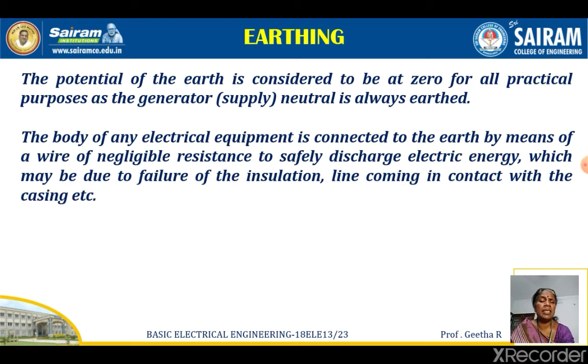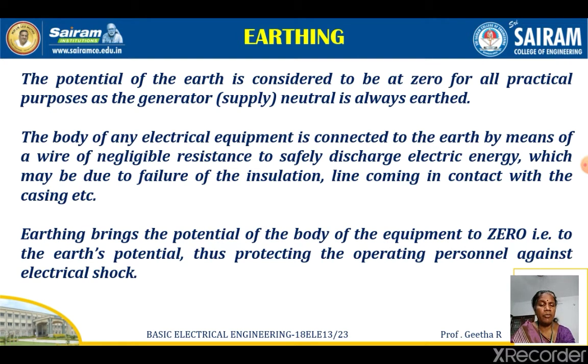Connecting the body of any electrical equipment to the earth by means of a wire of negligible resistance is nothing but earthing. It is for the purpose of safely discharging the electrical energy which is due to the failure of the insulation, or when a line comes in contact with the casing, etc. Whenever there is a fault, if the device is properly earthed, then that extra energy may be discharged through the earthing wire. Earthing brings the potential of the body of the equipment to zero, that is, to the Earth's potential, thus protecting the operating personnel against electrical shock.